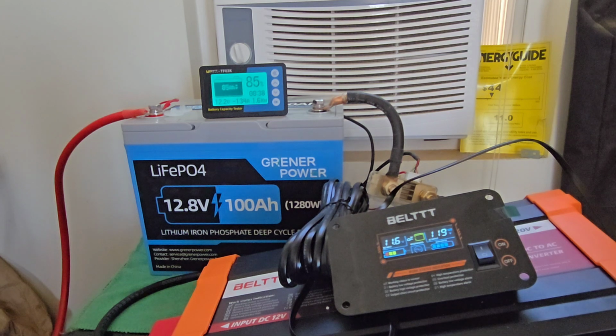All right, so let's see. Maximum continuous discharge current is 100 amps, so the BMS is set for 100 amps. If I go over 100 amps, it's supposed to kick off. Now, it's showing right now 100, minus 134 amps, so I'm over the 100 amps there, and it hasn't kicked off. The BMS has not kicked off.